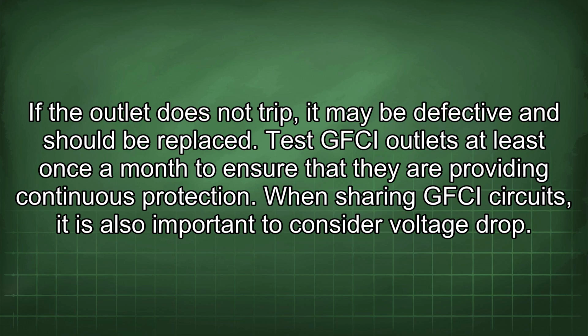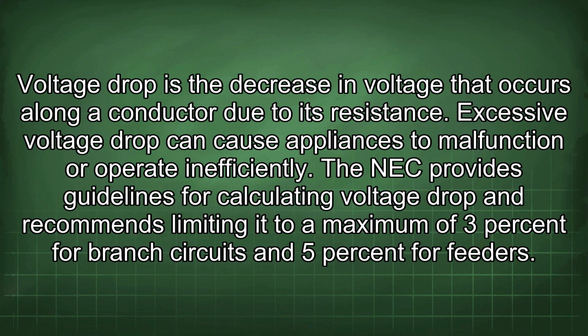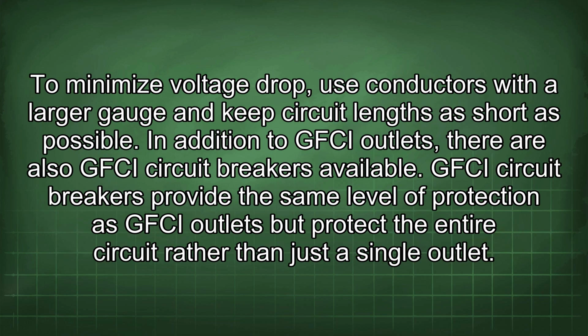When sharing GFCI circuits, it is also important to consider voltage drop. Voltage drop is the decrease in voltage that occurs along a conductor due to its resistance. Excessive voltage drop can cause appliances to malfunction or operate inefficiently. The NEC provides guidelines for calculating voltage drop and recommends limiting it to a maximum of 3% for branch circuits and 5% for feeders. To minimize voltage drop, use conductors with a larger gauge and keep circuit lengths as short as possible.